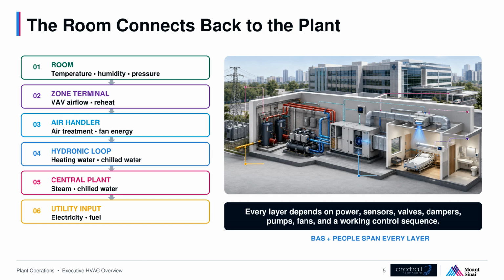To understand those dependencies, follow a room condition backward. The room depends on a zone terminal, often a VAV box, to control airflow and reheat. The terminal depends on stable air from the air handler. The air handler depends on chilled water, heating water, steam, electrical power, drainage, and controls. Those hydronic systems depend on pumps, heat exchangers, valves, and the central plant. The plant depends on electricity, fuel, water, and utility continuity. BAS controls and plant operations people span every layer. That is why a room complaint may be only the symptom. The root cause could be a local sensor, a VAV damper, an air handler coil, a pump sequence, or plant capacity. Project decisions also travel through this same chain, so changes must be evaluated as part of the complete system.